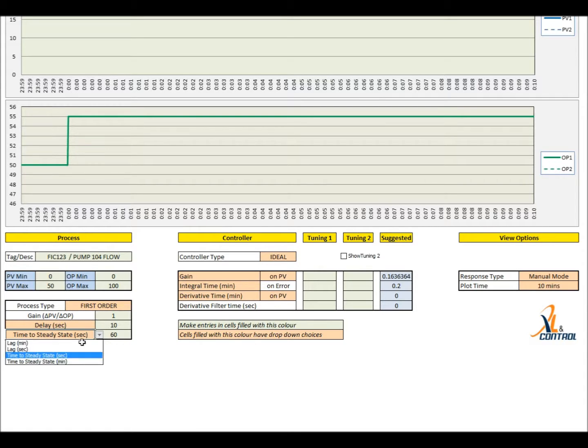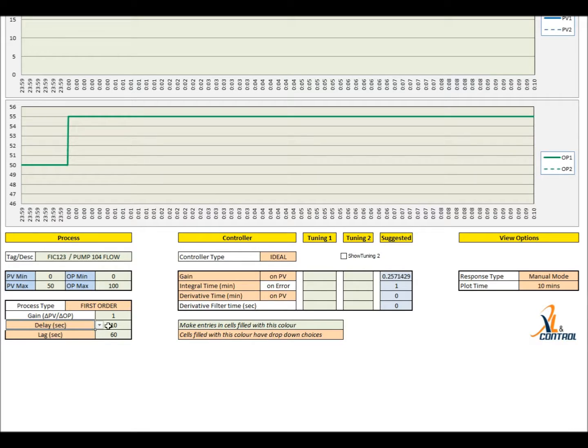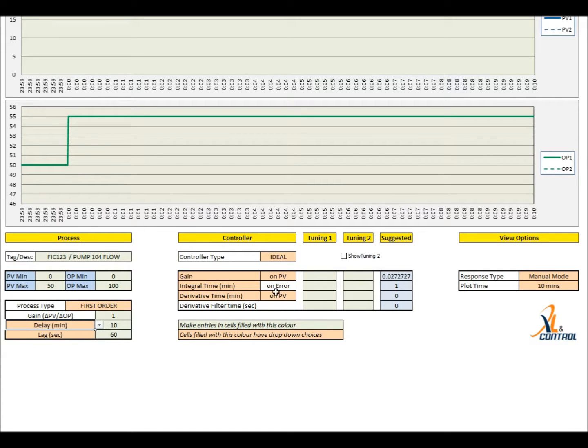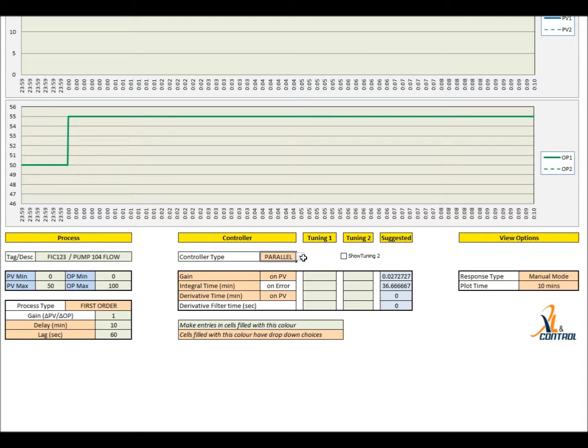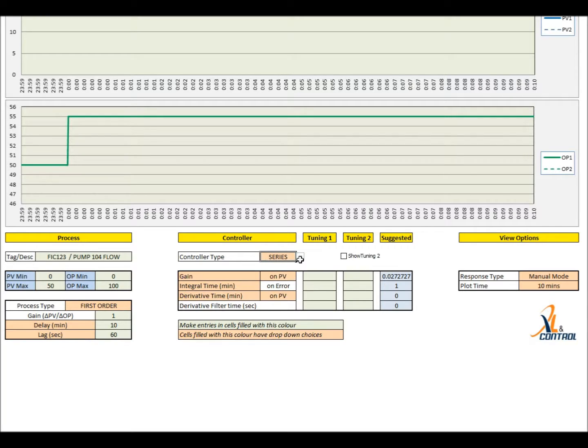Delay time can be provided in minutes or seconds. The tool can simulate series, parallel or interactive PID algorithms. Almost all PID algorithms on major PLC and DCS systems can be simulated with the spreadsheet.